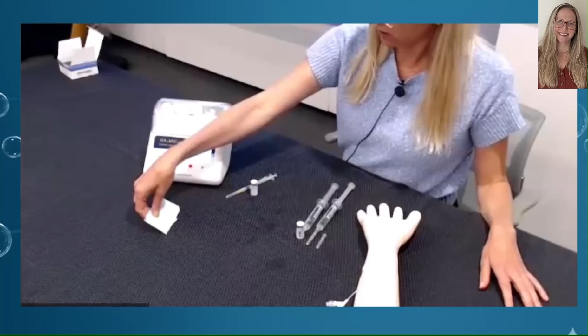So we're going to open up our Vialmix, push the lever over, and insert the vial. At the top, it automatically sets for 45 seconds. The Vialmix is a mechanical agitator. It has an automatic 45-second activation cycle. You want to ensure that once the Vialmix is started, you do not interrupt the cycle or lift the cover.